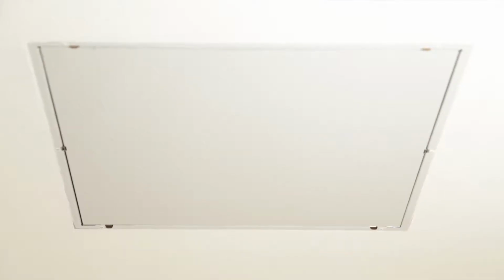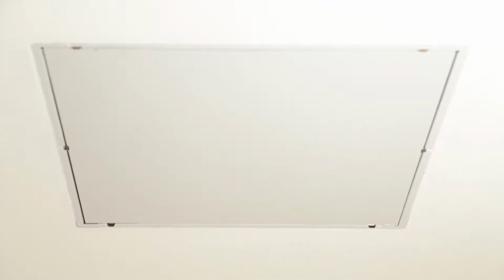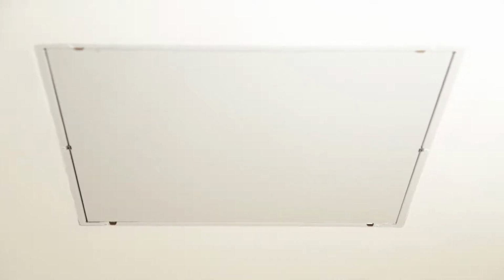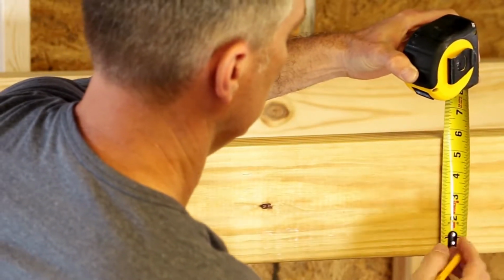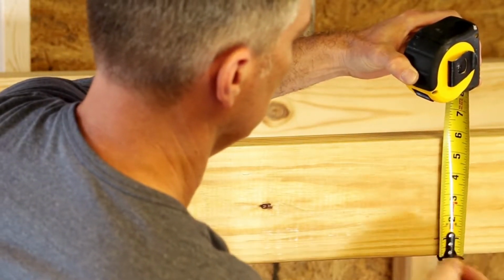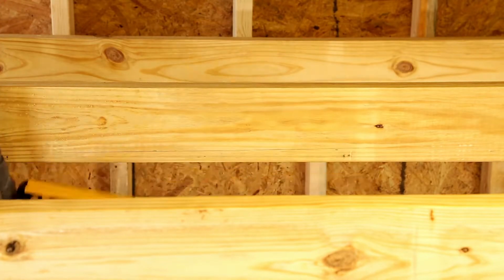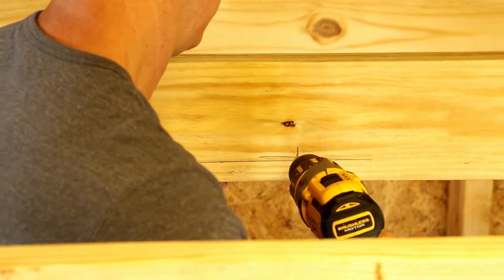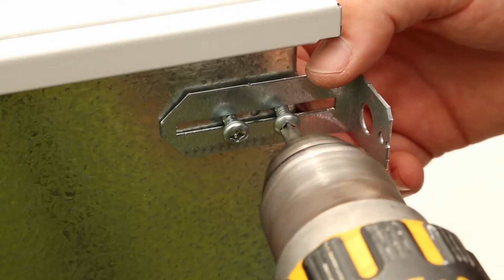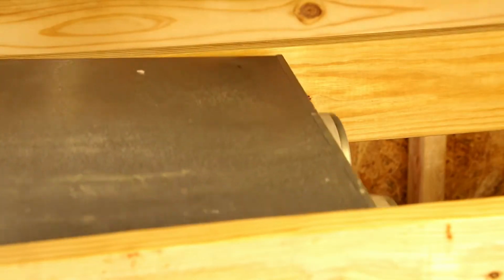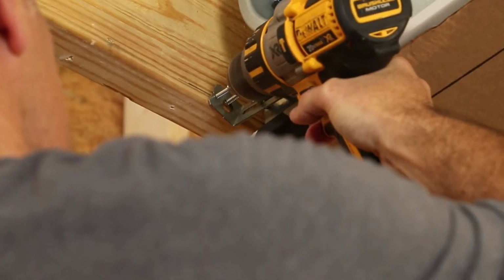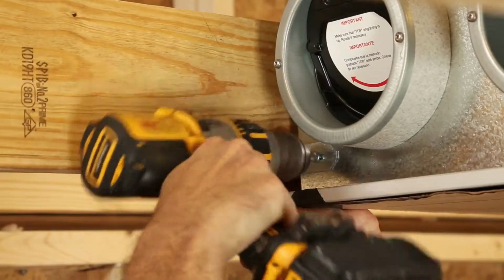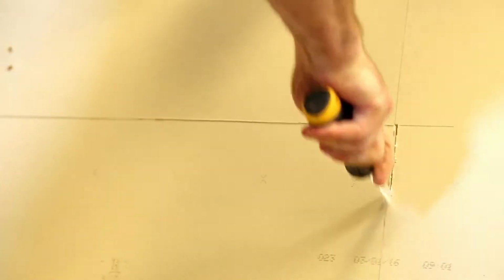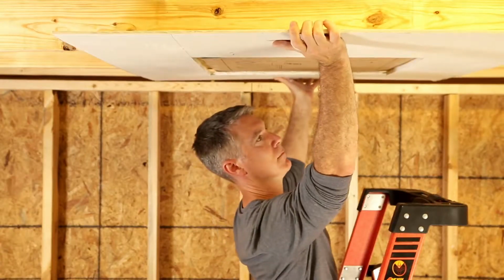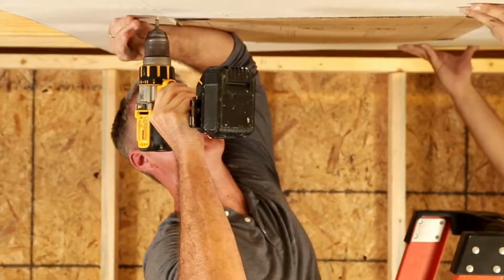If you're installing in the ceiling with the unit cover flush with the ceiling, the unit installs in much the same way as previously described. When installing 1/2 inch thick drywall, trace your level line on both trusses 1 inch from the bottom of the trusses. Attach your hanging screws to the trusses. Mount the brackets to the unit, hang the unit on the truss. Secure the unit to both trusses, and secure the brackets to the unit. Cut a hole in the drywall so that the drywall fits around the unit, and secure drywall to joists.